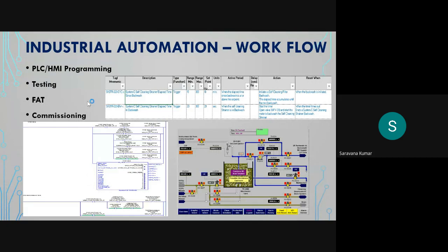Then we proceed with the PLC HMI programming. Once we have done the programming, we have to do internal testing with the simulators. And of course, once we have completed everything, we have to do the factory acceptance test. The factory acceptance test may be in-house, meaning wherever you are working. There, the customer will visit, and we have to show what they are expecting. And the site acceptance test is also there. We have to go to the site before commissioning. We have to prove to the customer, okay, these devices are communicating this way, as you said.